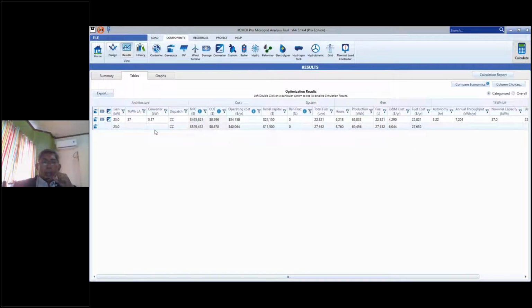If we look at the previous system modeled using a 23 kilowatt genset, our net present cost is 529,442. But adding a battery that HOMER modeled, recommending 37 pieces of 1 kilowatt hour lead acid battery and a 5.17 kilowatt converter, our net present cost went down to 465,621, and our cost of energy also dropped.